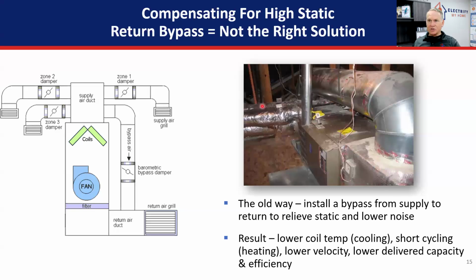And we would need each side of the duct system, with one side open or one side closed, or upstairs open, downstairs closed, whatever. They need to be able to produce 350 CFM per ton out of either side. So really the only way we can do that, if we want to run a system that can actually heat and cool the whole house at one time, is a staged system. So we need a staged zone board, so that when one zone closes, it operates off a percentage of zones and just goes back into low stage for heating and cooling.